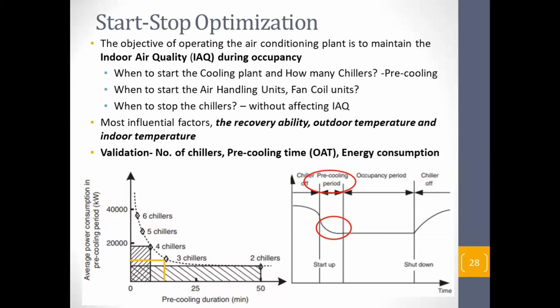Not before 8 o'clock. At 7:30 it doesn't need to be 24 degrees. So then, if you start your chillers at 7:30, can I bring down the temperature to 24 degrees by 8 o'clock? Right? That is the question. So you can do a little bit of trial and error and decide whether you want to run 1 chiller or 2 chillers. That's trial and error.